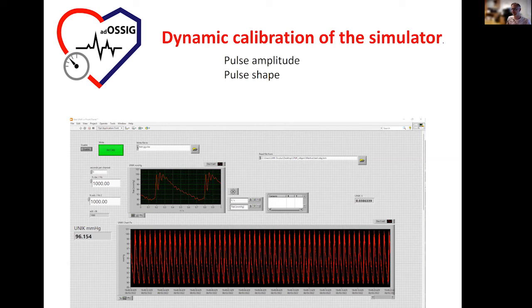The simulator is by definition an electromechanical device which has some problems, or it cannot be absolutely accurate. And it also ages, and the materials get tired and so on. So the time drift is expected. Another thing which we did out of such a test was also evaluating the pulse shape. And the pulse shape is shown here. The pulse shape, meaning one such pulse, was done in such a way that we segmented this pressure pulse waveform, and then compared different shapes.